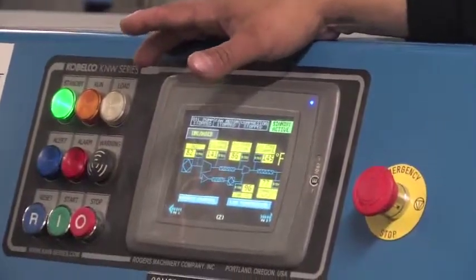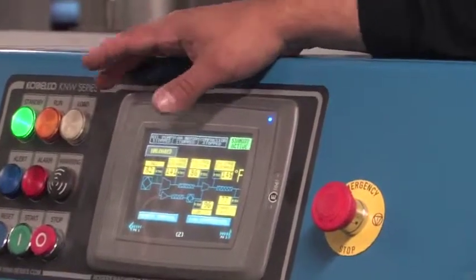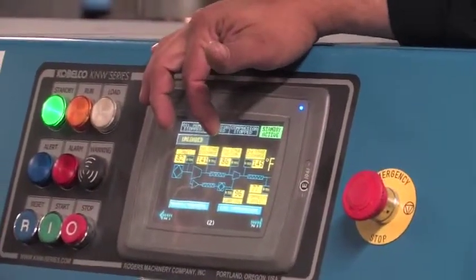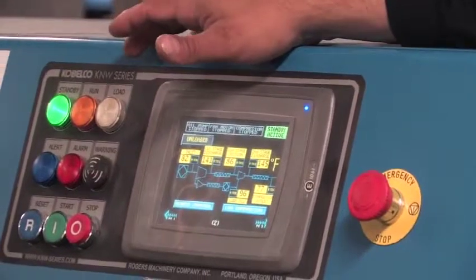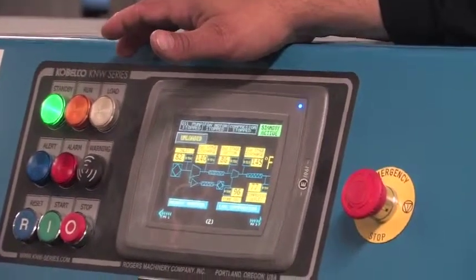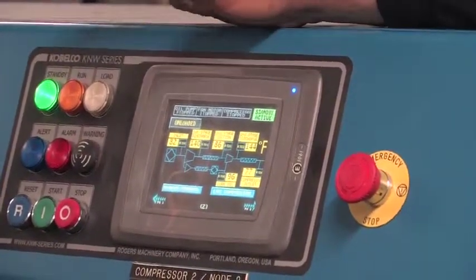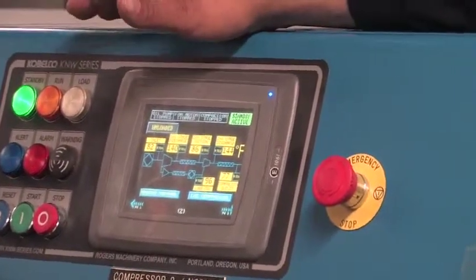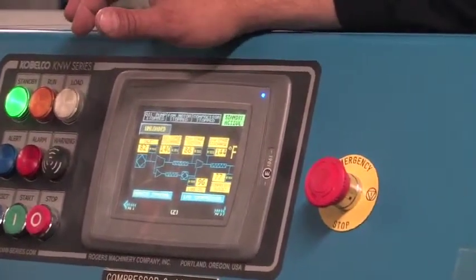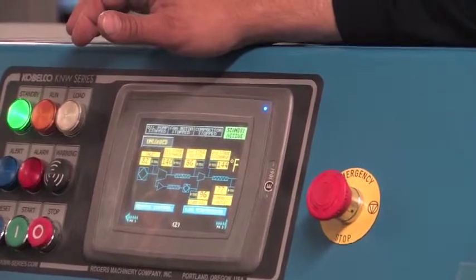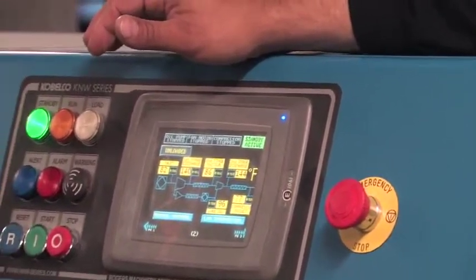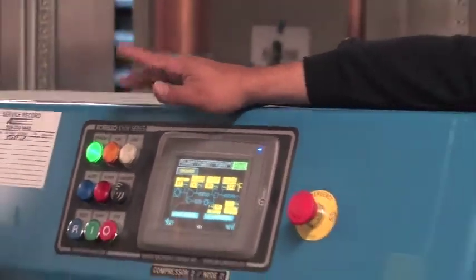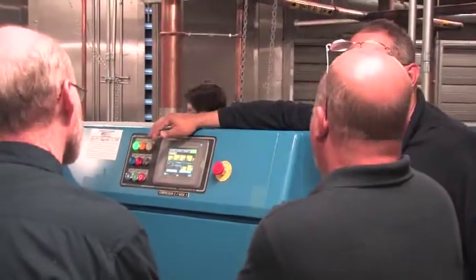You're actually looking to have it within 20 degrees anyway. You're really looking, as long as this is below about 125, you're okay. They don't want it much below 100 though, right? They want to see it somewhere 75 to 125. The real trick is you don't want to go down into like the 60s, because then you're making condensation. It's actually about 65 or 70 that you'll start making condensation.